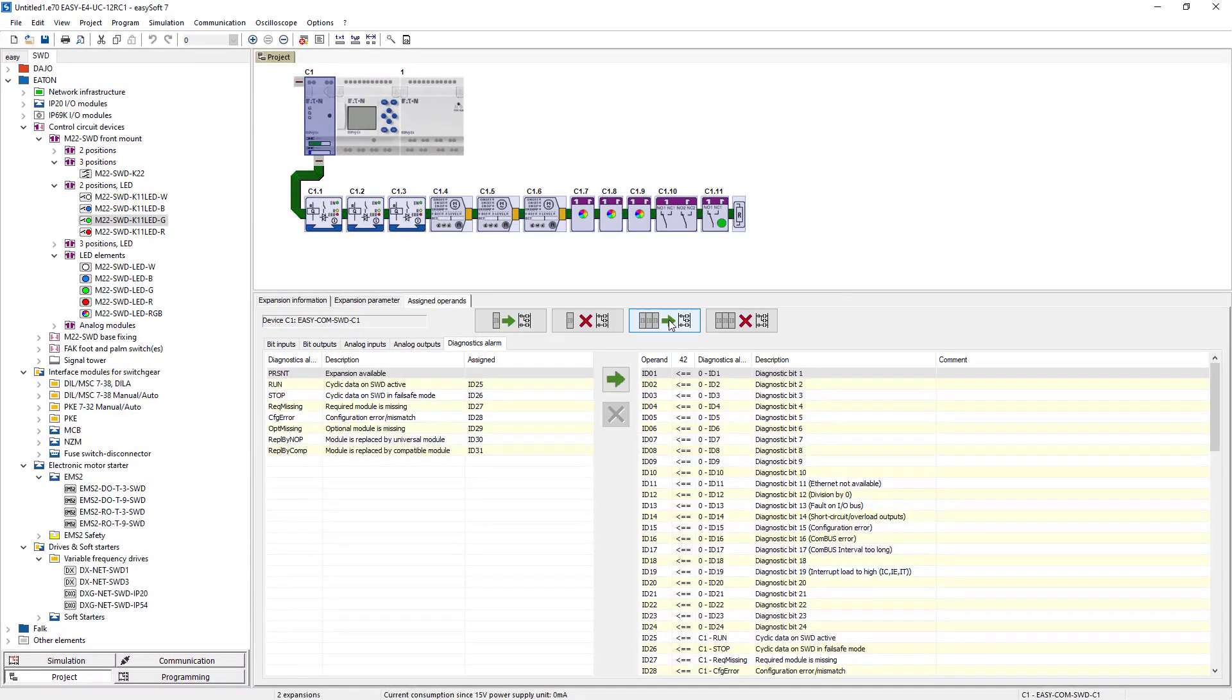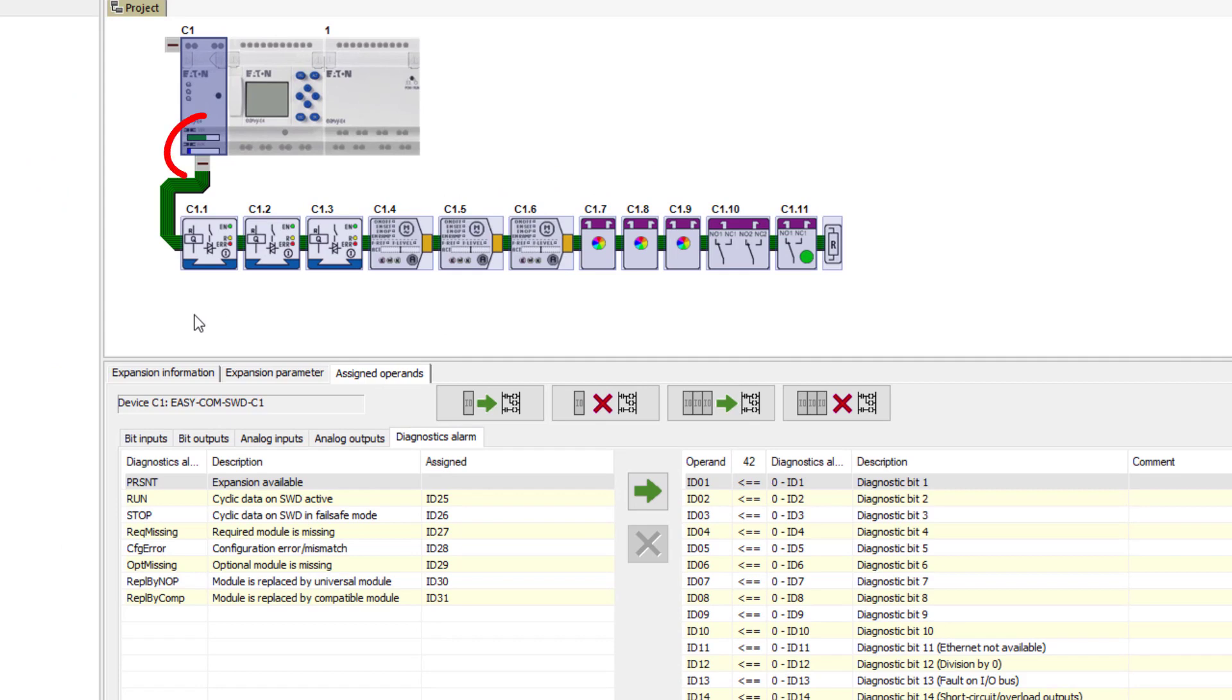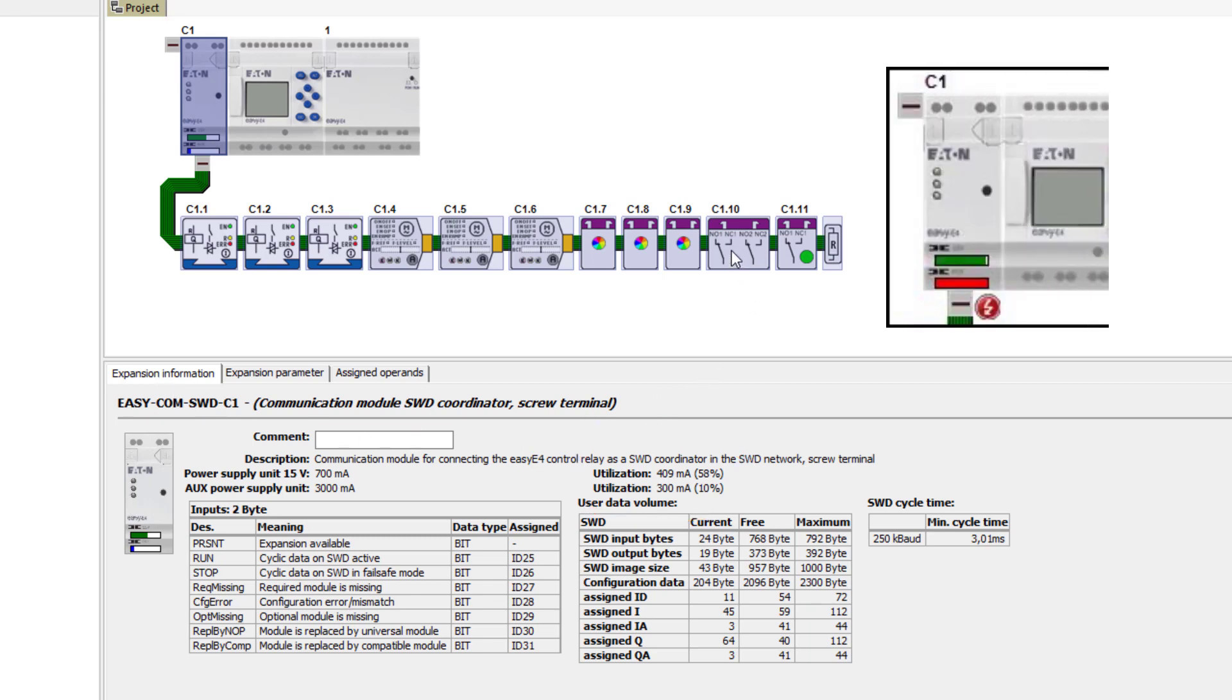The current load of the SWD line will be displayed as a bar graph in the SWD module itself and in the expansion information tab. In our example, the 15V DC is loaded with 58% and the 24V DC with 10%. An overload of the respective voltage would be displayed with a full red bar graph.